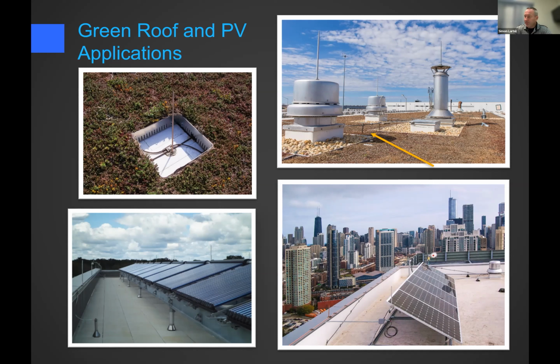But the last time I had any numbers on this was at a project that covered most of a big Canadian Blood Services roof, and they ran the numbers after the lightning protection went in, and it was doing 0.2% of a hit with the shading to the overall generation capacity of the system. So not that big a deal, but occasionally the PV installer gets tight about that. So we just have to work with them to try and minimize the shading issues.